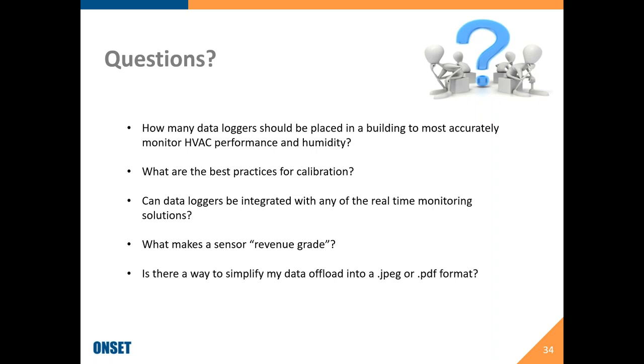If you're taking, for example, the UX120006M, the four-channel 4 to 20 milliamp logger, any third-party sensor with a 4 to 20 milliamp output can be integrated with this device. However, this specific logger will not have the excitation power generally to power that third-party sensor by itself. So it's important when you're using a logger like this without that excitation power to ensure that you have a localized power source, whether that be some sort of DC battery or arrangement locally to power the sensor on an ongoing basis.